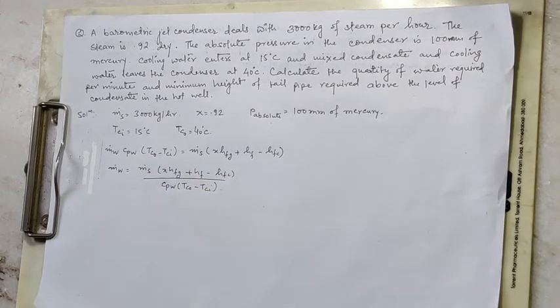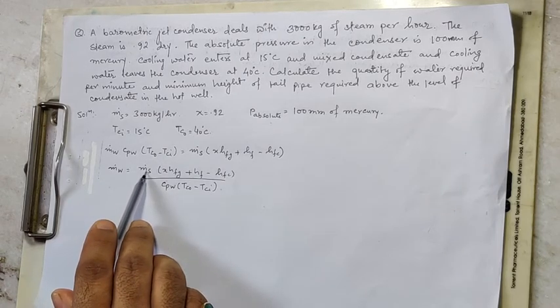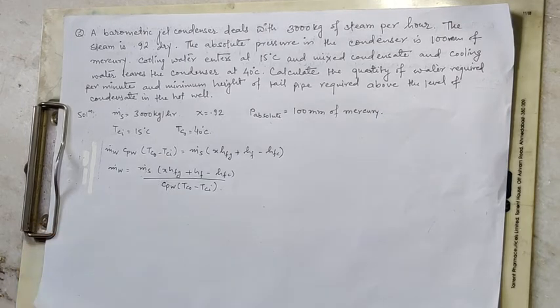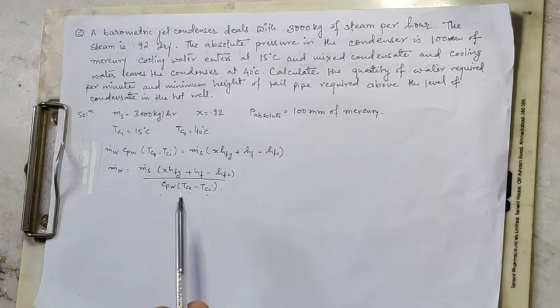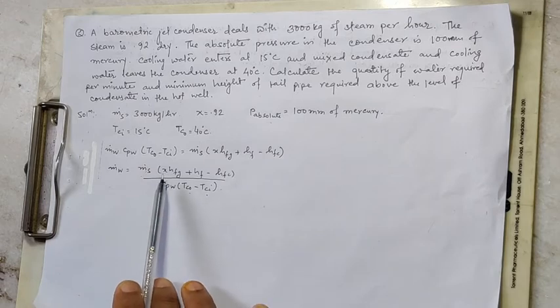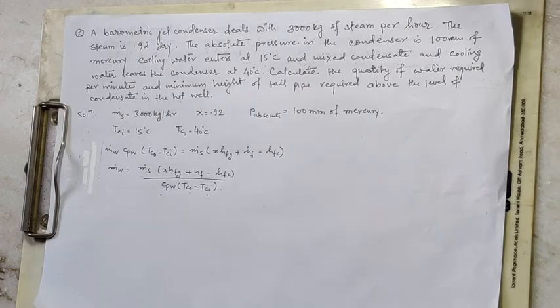Mass flow rate of steam is given as 3000 kg/hr. cpw (specific heat of water) is 4.187 kJ/kg·K. Tco is 40°C and Tci is 15°C. x is given as 0.92. Now we need to find the enthalpies hfg, hf, and hfc from steam tables at the condenser pressure.